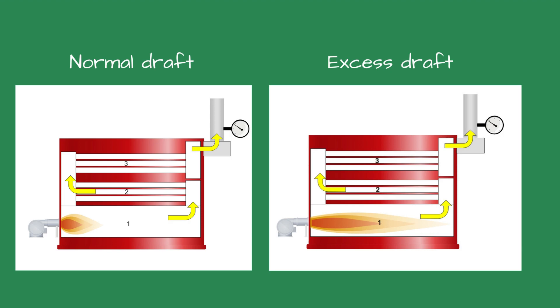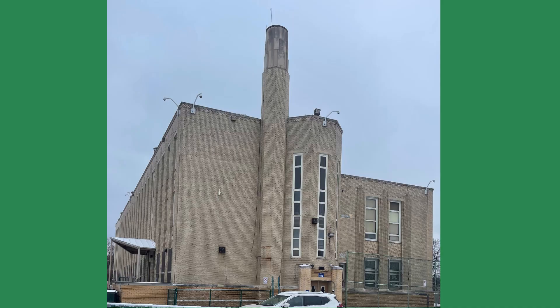After the burner shuts off, the chimney draft can pull the heat from the boiler. When a boiler manufacturer tests the efficiency of their boiler, the test parameters require a six-foot-tall stack or chimney. In most real-life applications, the chimney may be much taller.